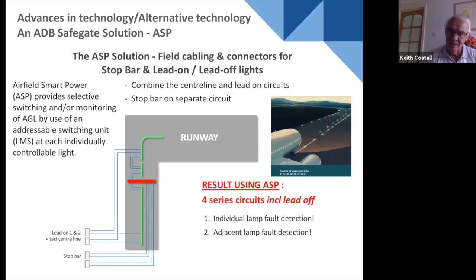If we look at a typical dual stop bar scenario on an airfield, with traditional AGL, we have something like 64 circuits and over 200,000 meters of primary cabling, for a dual stop bar with associated taxiways and lead on, lead off lights. That's one hell of a lot of infrastructure to install or maintain.